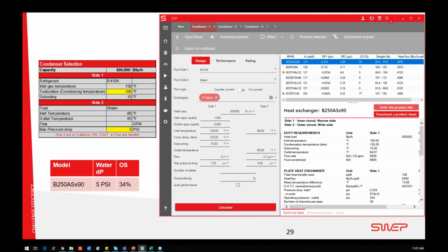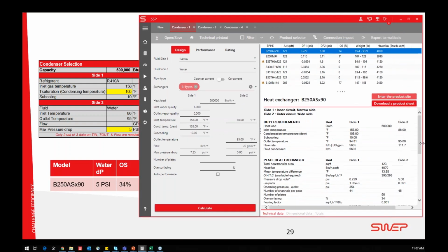I'll extend it a little bit. The temperatures we entered were 86 to 95, and with the BTUs and everything, the water flow is calculated by SSP to almost 112 GPM. Let's say we can reduce the flow a little bit. We can accept a higher water out temperature. Instead of 95, let's go 97, but keep the 5 psi. You don't want to accept a higher pressure, but let's go up 2 Fahrenheit. What happens then? And voila, we go down 18 plates.